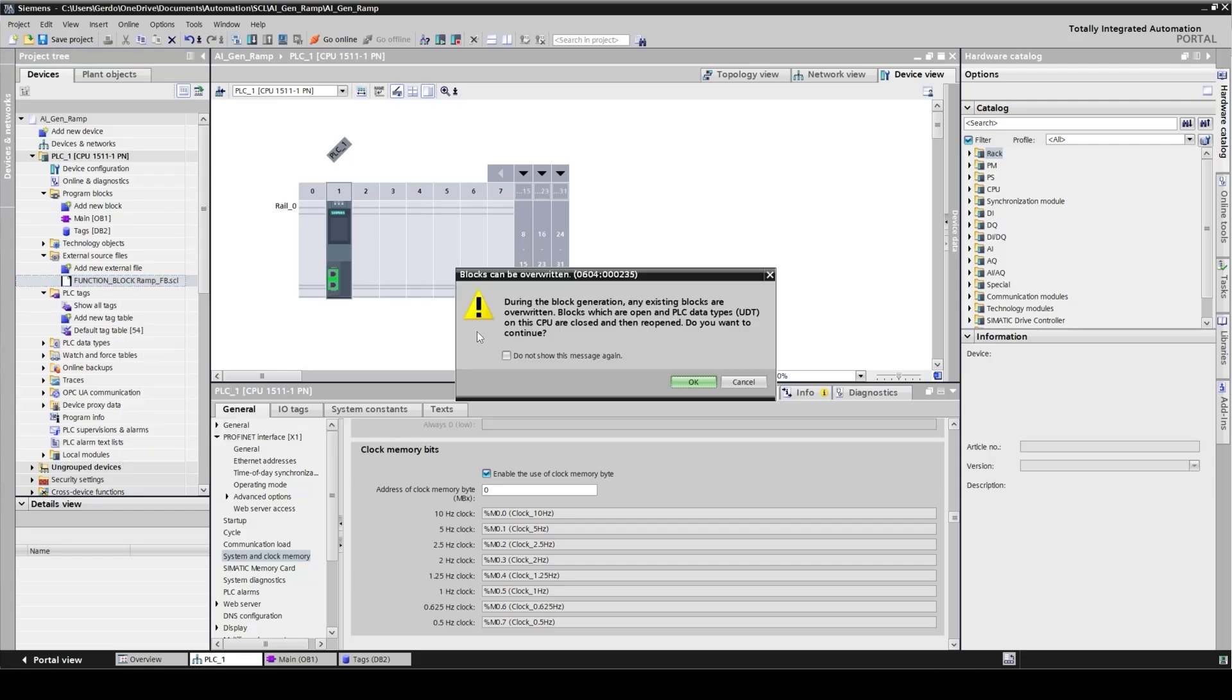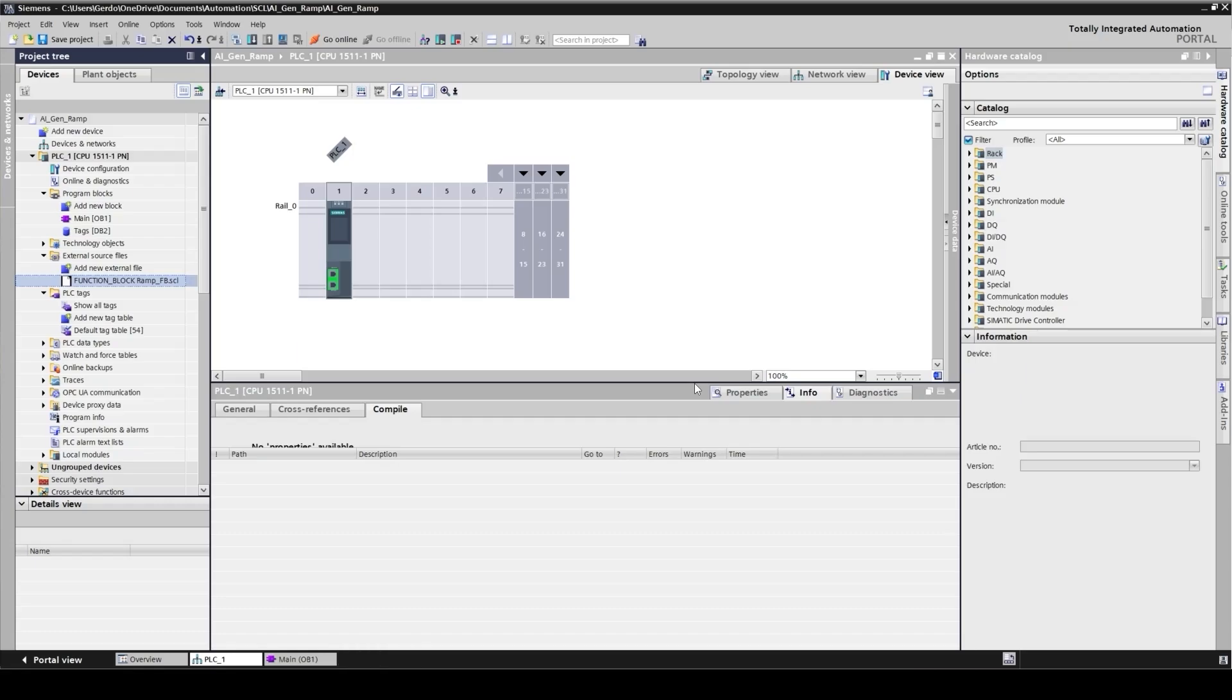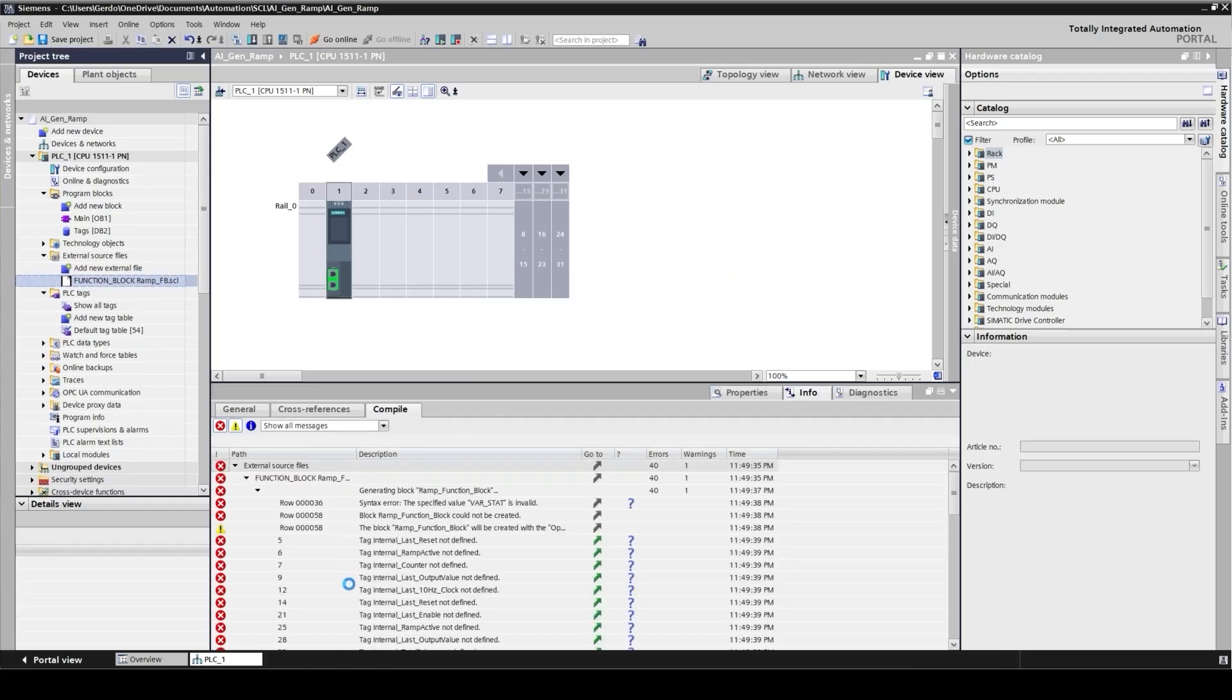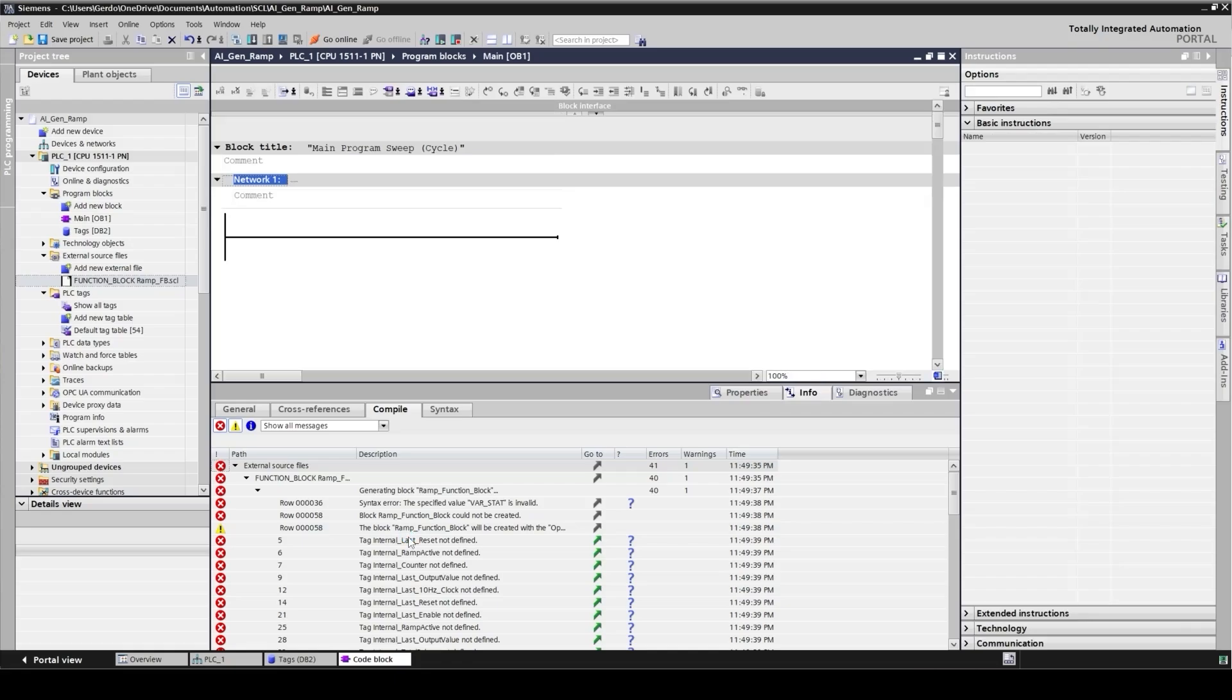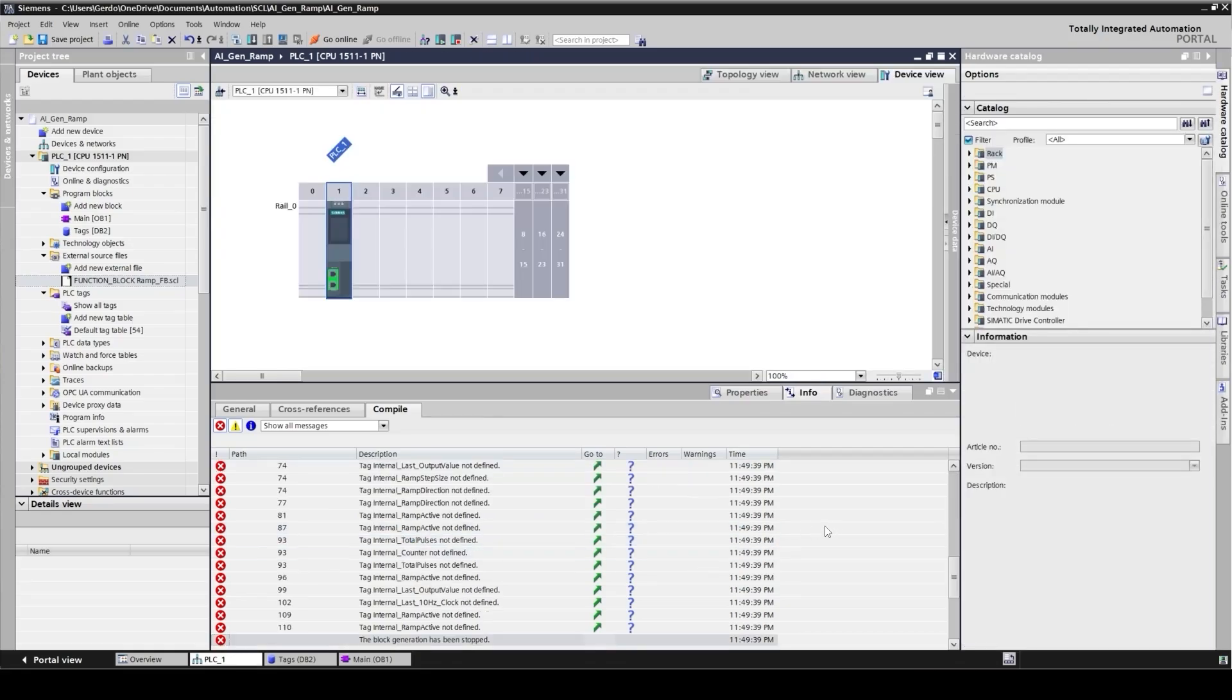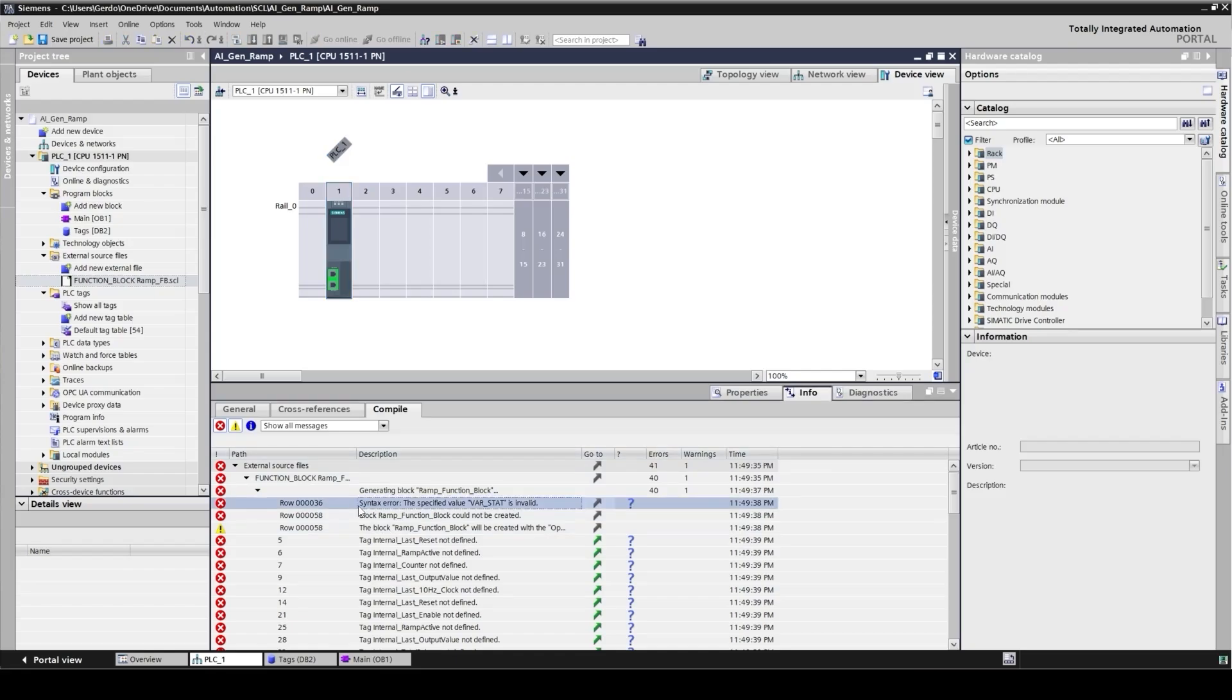When I click on this option it tries to compile the code and generate a function block in my PLC program folder. Here it gives me a heads up that during this process some new UDT might be generated. Click ok and then we can see the process started here. I got several errors. Let's see what we have here. I scroll up to the first line of the errors. It starts with the syntax error. The specified value of var stat is invalid. Probably a keyword that is not acceptable for TIA Portal has been used in the code.